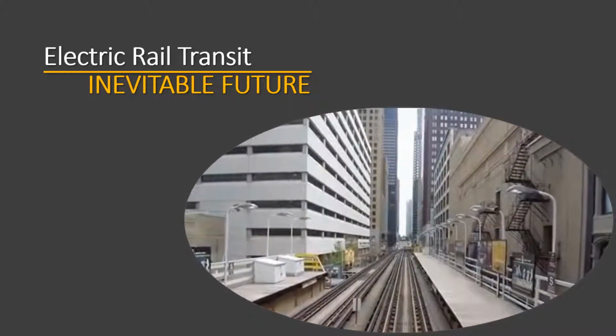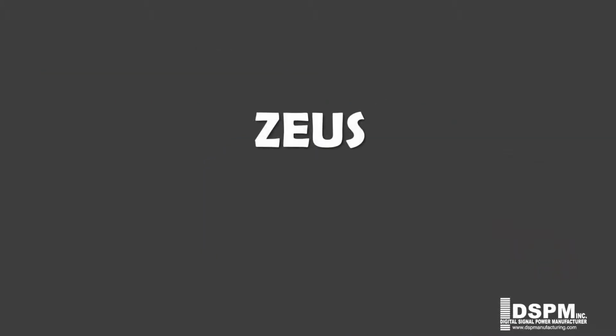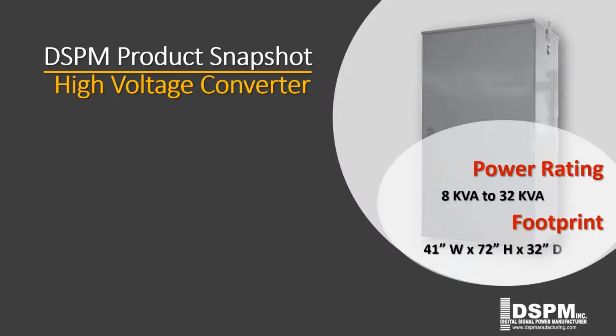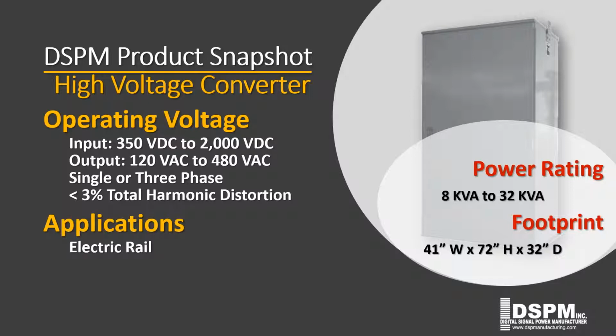To address this challenge, we've created the only Made in America solution and the newest member of the DSPM family of products, which is currently employed by the Chicago Transit System: Zeus, DSPM's high-voltage DC to AC converter. Available 24 hours a day, 7 days a week, DSPM's Zeus high-voltage DC to AC converter stands ready to seamlessly convert thousands of volts of direct current used to power electric rapid transit trains into usable 120 to 480 volts of alternating current to keep communications, lighting, safety, and control systems operating. Rated from 8 kVA to 32 kVA, DSPM's high-voltage DC to AC converter is a powerhouse every electric rail line needs to ensure its travelers' safety.